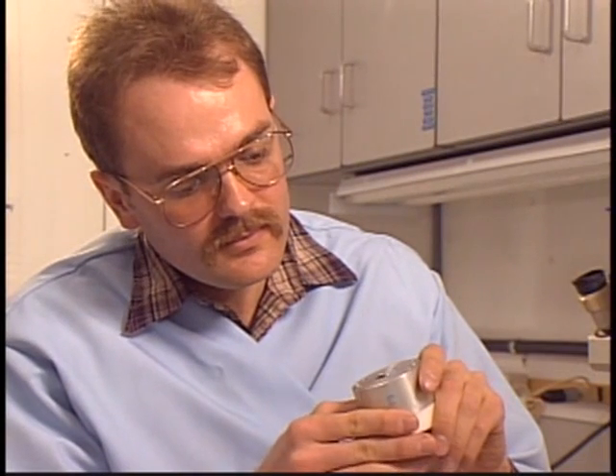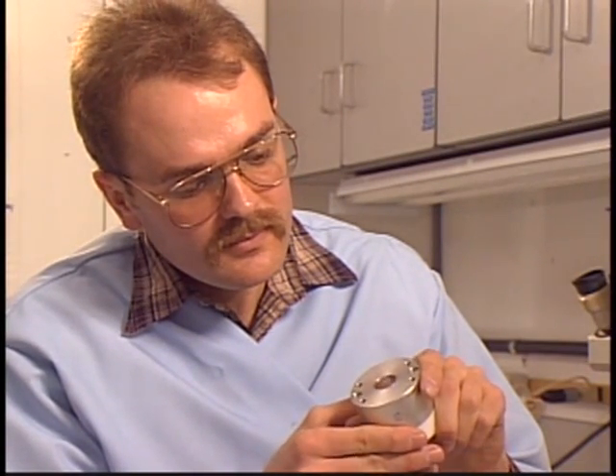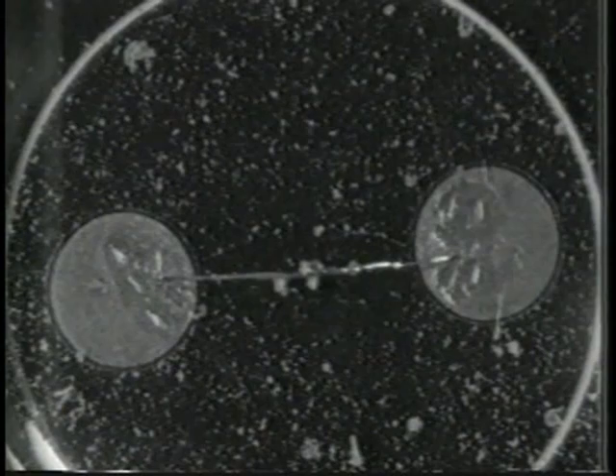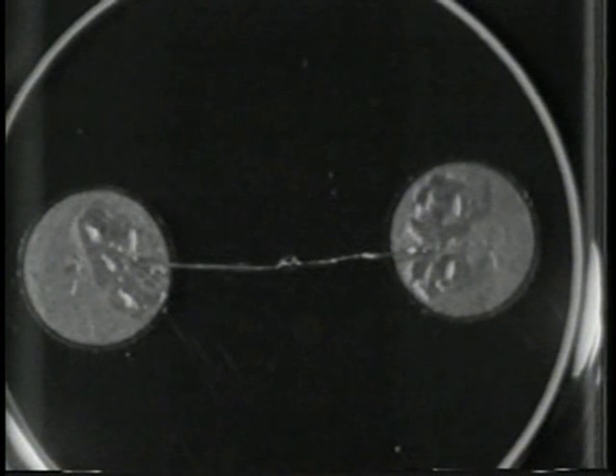Take out the screws, disconnect the cable, and look at the thermocouple sensor head. Under a microscope, a moderately contaminated thermocouple looks like this. After you clean it, it should look like this. The small wire structure is the thermocouple itself. Notice that the wire is arched. If yours is bent or flattened, stay tuned, we'll tell you what to do. The surrounding metal is called the thermocouple mount.